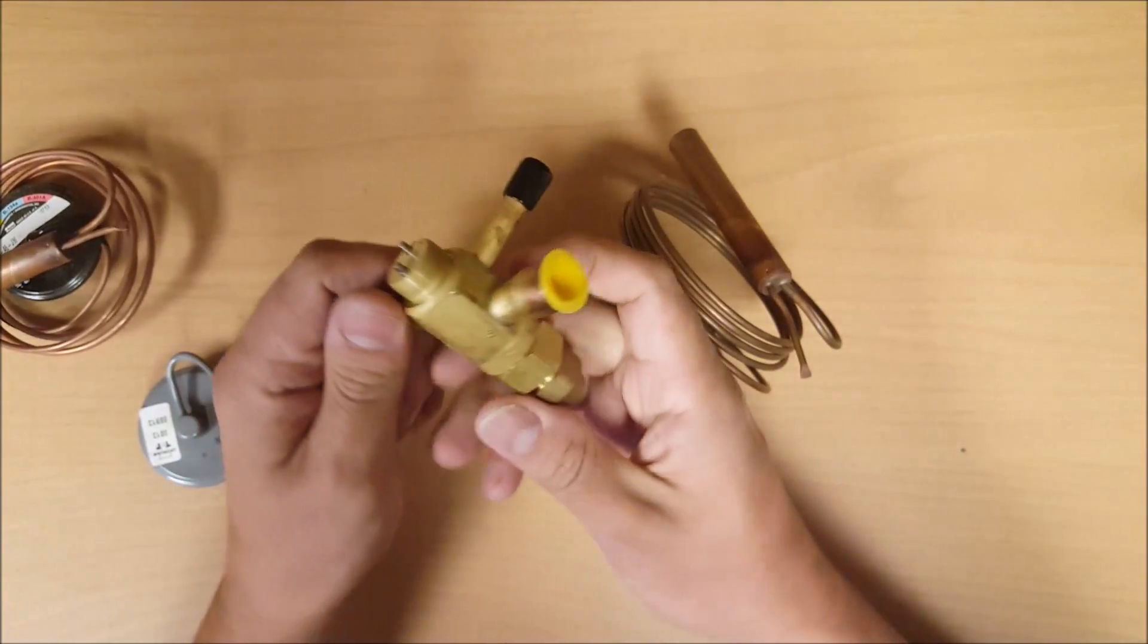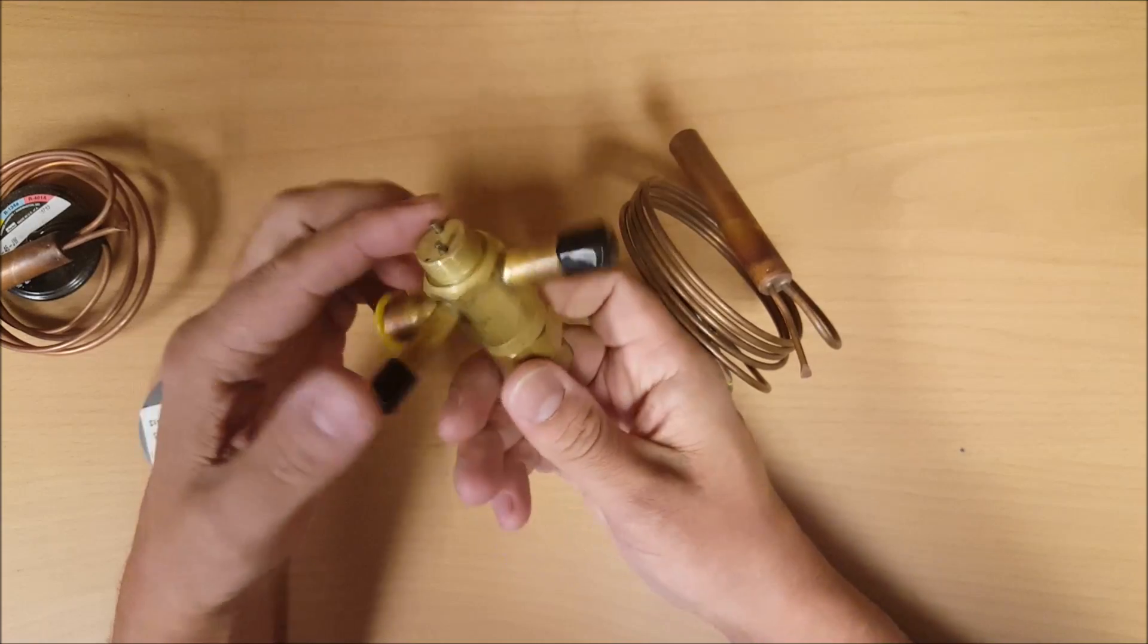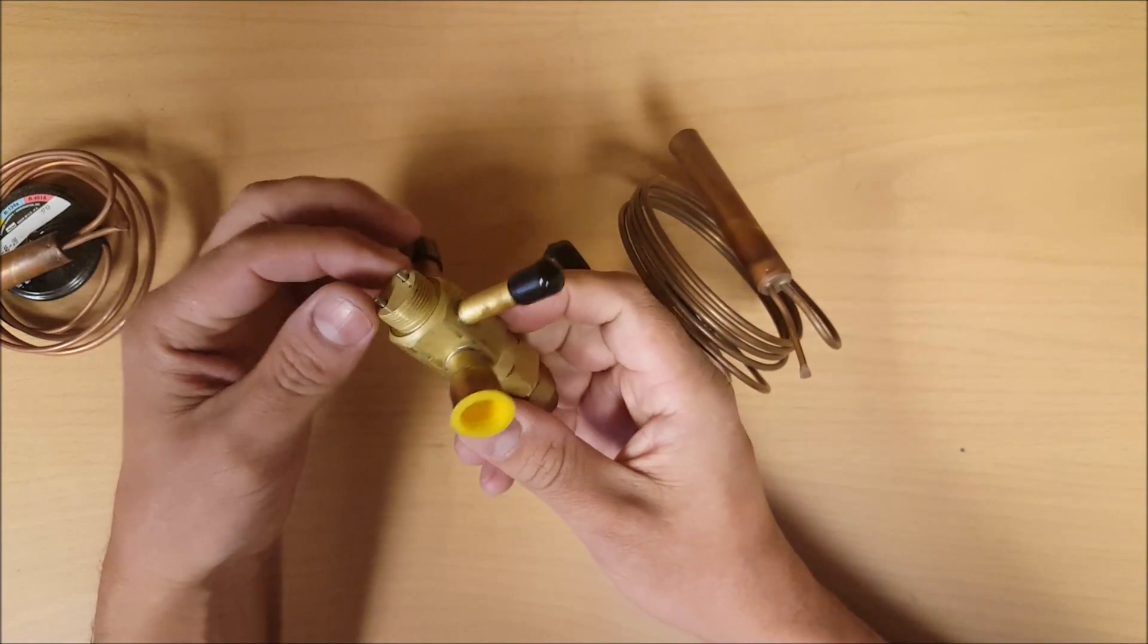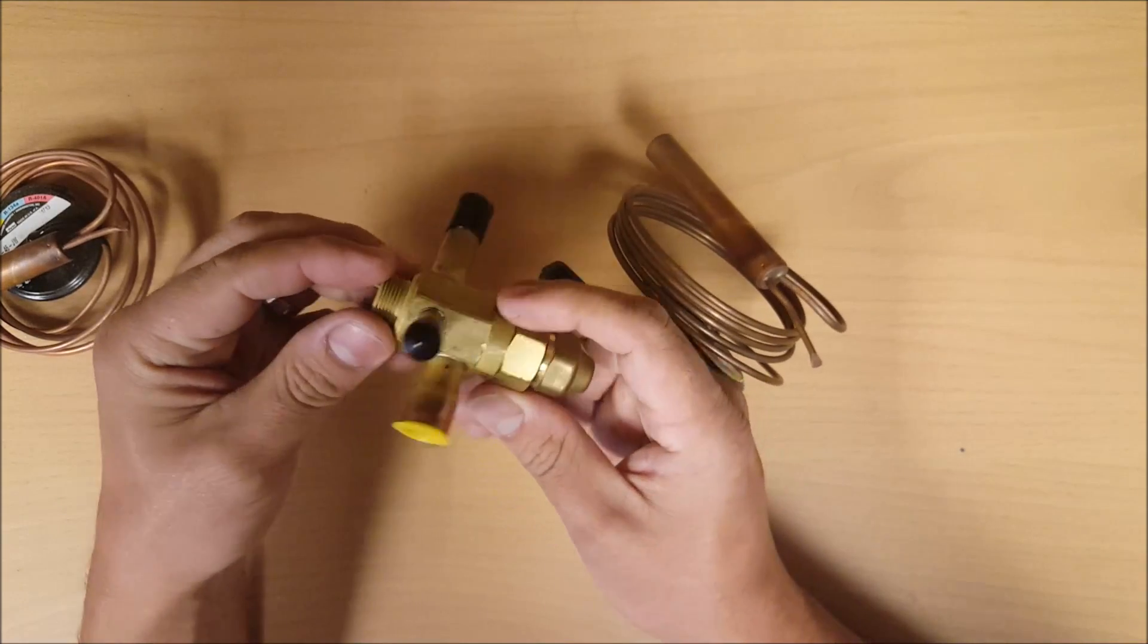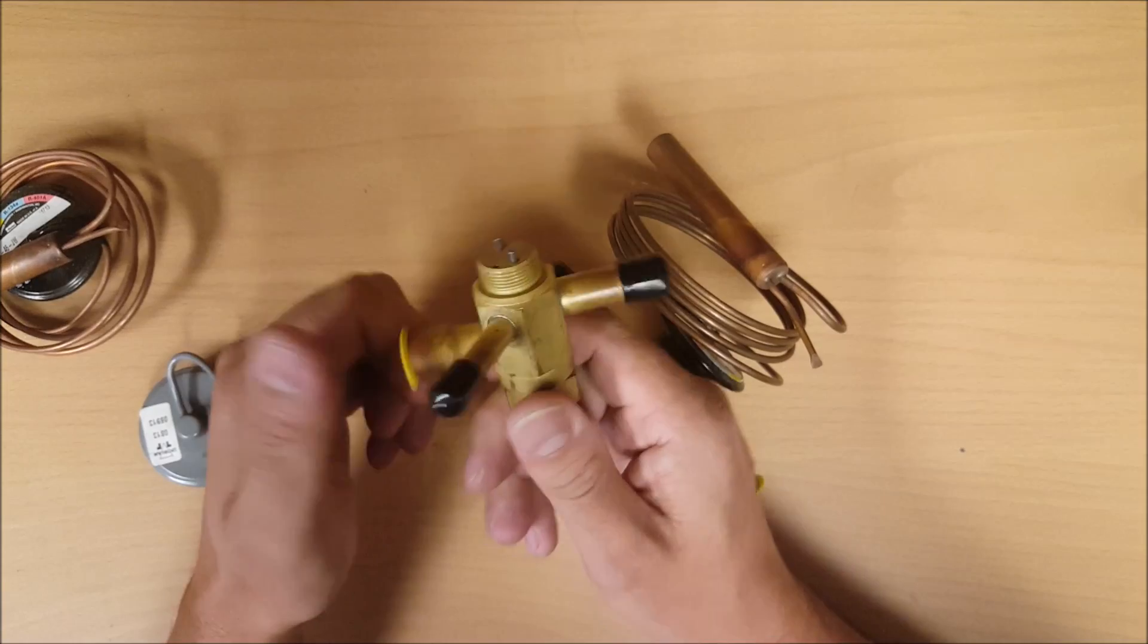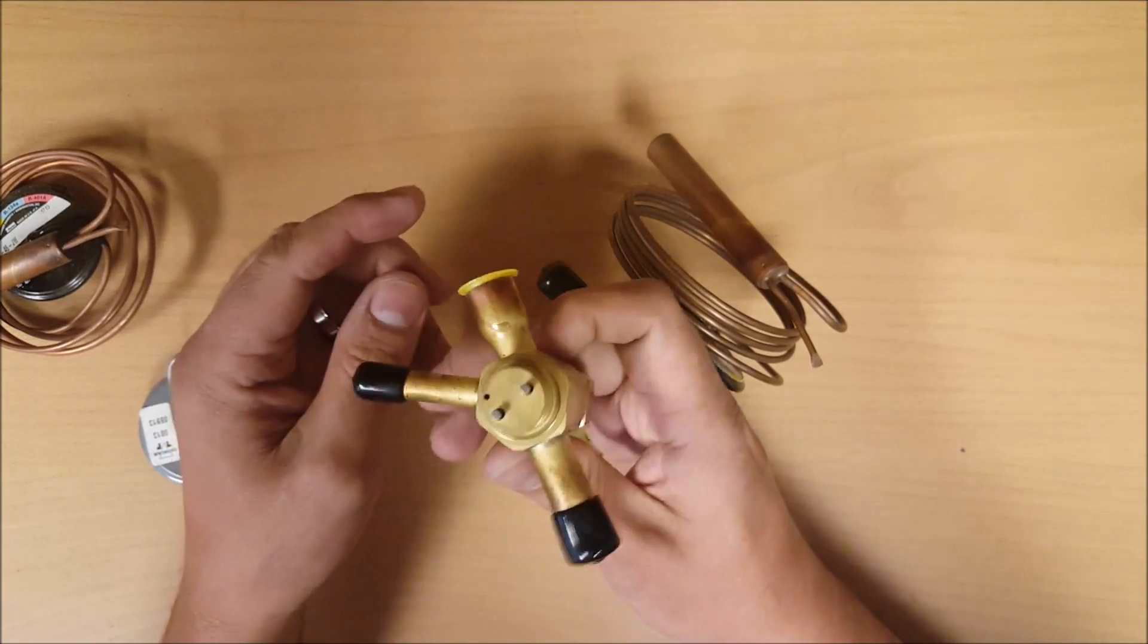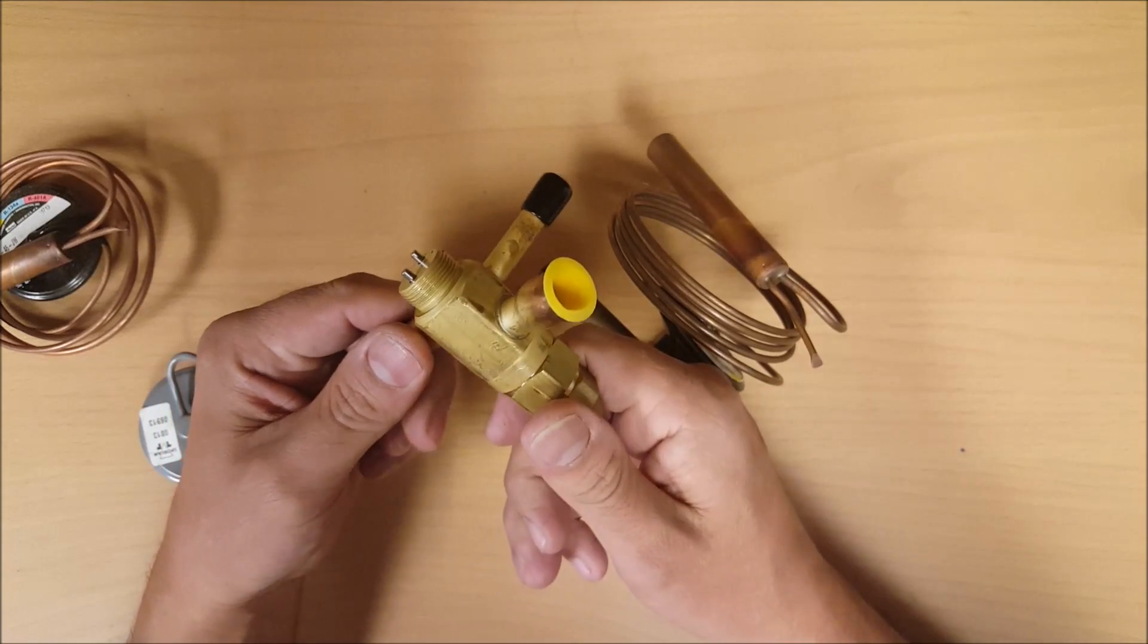The valve body itself is going to regulate the amount of refrigerant into your evaporator. This size is based on your BTUs of your unit, and these are rated in tonnage. If you've got a 12,000 BTU evaporator, that's a one ton system. You would need a one ton valve.